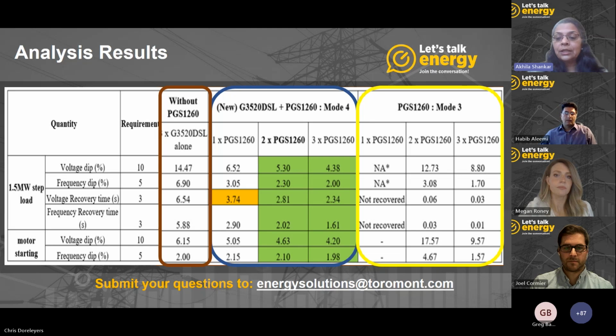So for the combination of 3 gensets plus 1 battery energy storage system, you will see in the 5th column that this did not meet the requirements in terms of the voltage recovery time. The customer's requirement was that it has to recover within 3 seconds, and you can see, highlighted in the yellow box, the recovery time was around 3.74 seconds. The same set of 3 gensets, 2.5 megawatt rated, in combination with 2 battery energy storage systems, 1260 kilowatt rated, meets all of the requirements of voltage dip, frequency dip, and recovery times as stipulated by the customer.